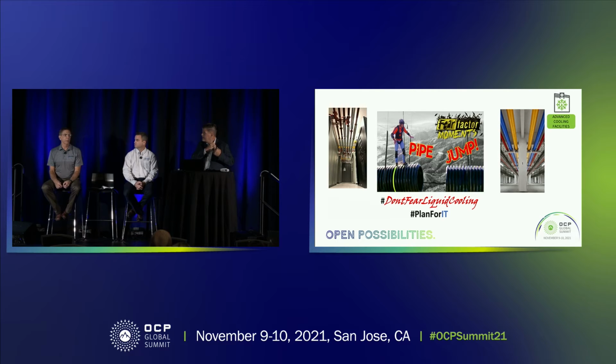In 2013, he could see the future, at least from where he was sitting, probably from clients that he was dealing with, is what I'm guessing. Back in the same chair I was able to occupy at Intel, you knew we had to do something different in the next 10 years, because Intel used to have a 1-year, 3-year, 5-year, and 10-year model. And by 2025, there were no known solutions in the air-cooled space. So liquid became a natural. Personally, I prefer immersion over plates and other discussions, because you got to get there anyway. But I defer to the plates because it's the same infrastructure, so I can just move from the plate environment to immersion from a design standpoint.